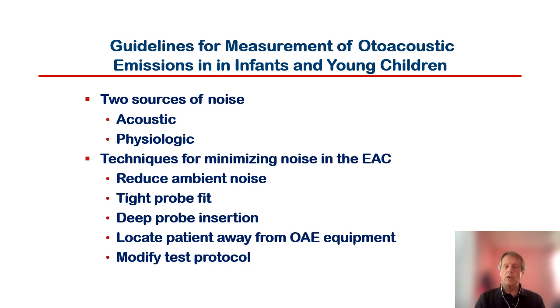So it's very important to do everything in your power to quiet the baby. A sleeping baby is not necessary for OAEs, but a quiet baby is. And it's also important to make sure that the environment is as quiet as it can be. A tight probe fit, a deep probe fit is a good beginning strategy. Closing the door to the test room, turning off equipment that's not needed, telling everybody in the room to turn off your cell phone, trying to eliminate external sources of sound. Usually all of that is adequate in reducing the noise level in the child's ear canal so that we can actually detect the OAE.